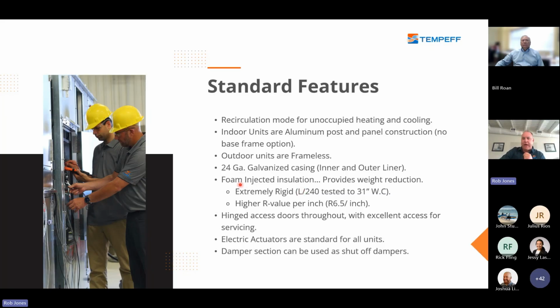Our standard is 24 gauge galvanized steel. We can do any gauge steel if you want. We can do stainless steel. We can do marine grade aluminum, whatever you wish. The reason why we can use 24 gauge is we use a foam injection process in all our panels. This makes them extremely rigid with a higher R value. Hinged doors throughout for easiest servicing. Electric actuators are standard, and the damper section can be used as shut-off dampers, which you saw.